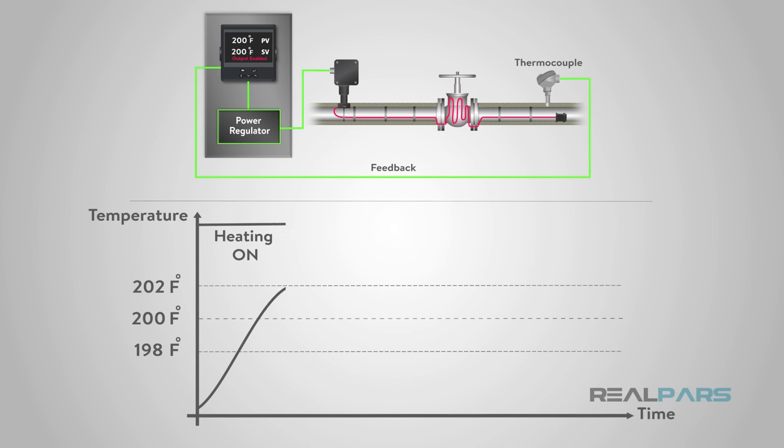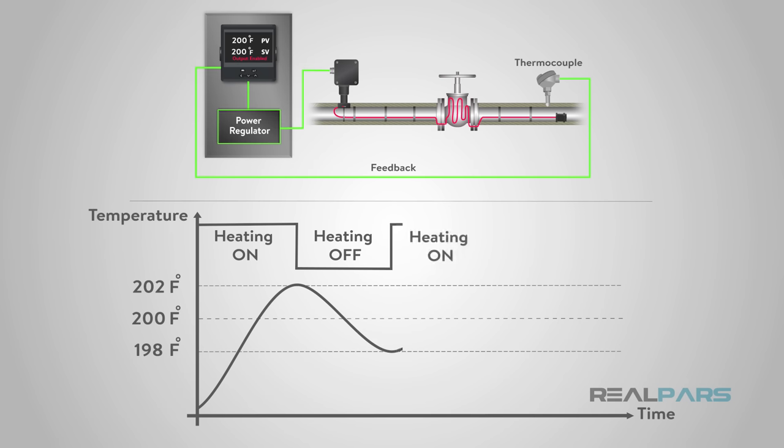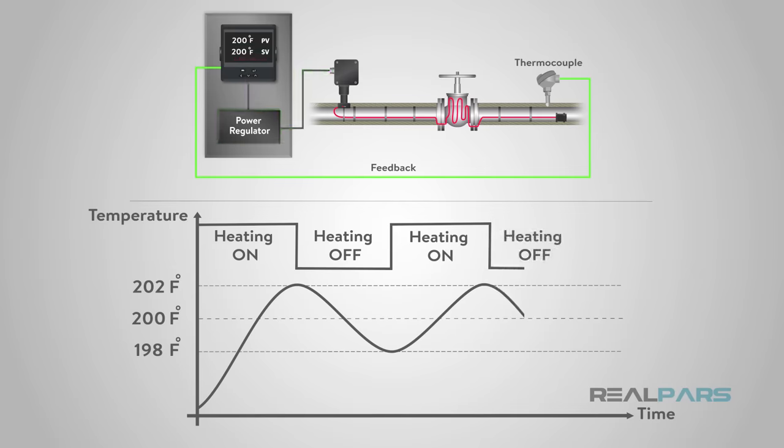When the thermocouple reads 202 degrees, it will turn the heat tracing off. When it reads 198, it will turn it back on. This is the simplest form of PID control.